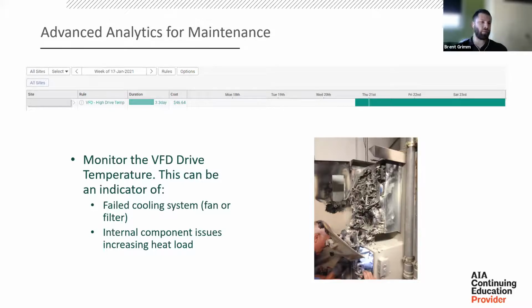We can see here where this started triggering a fault detection alert on Thursday the 21st. This allows an operator to get out there and get ahead of it. It's a whole lot easier to change a filter, a fan filter, clean a filter, and get that cooling system working, or even just take the piece of equipment out of service if there's a redundant piece of equipment that can take its place.